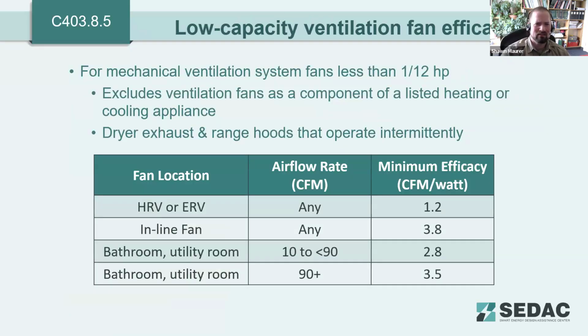Low capacity ventilation fan efficacy. So this is looking primarily at residential style spaces in commercial buildings where you've got kitchen exhaust vents or restroom fans, things like that, that are smaller in size. This table has been slightly updated to align with the residential ventilation fan efficacy requirements. So it's a pretty significant overhaul from the 2018 IECC requirements for small horsepower fans. Electrically commutated motors with 70% efficiency, which must have adjustable speed, was the only requirement in the 2018 IECC. So now you've got this table of requirements where you have to meet the fan efficacy as well.